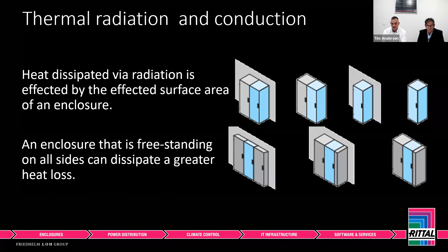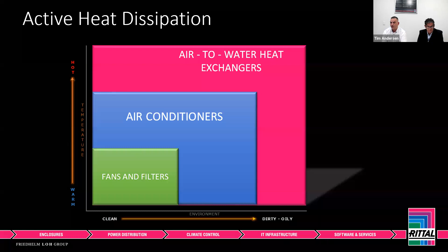Again, taking a closer look at active heat dissipation. We refer to this as products that actively dissipate heat by using a form of cool air. The graph here gives us a quick visual snapshot of our products on offer. It's a selection graph for cooling power requirements versus environments they are exposed to. Taking a look from the bottom, we have fans and filters, then air conditioners and air to water heat exchangers. Fans and filters are capable of working with favourable ambient temperatures, suitable from clean to moderately dirty environments. On the other end of the scale, you have the air to water heat exchangers that have a lot more cooling power and are able to cope with harsher environments.